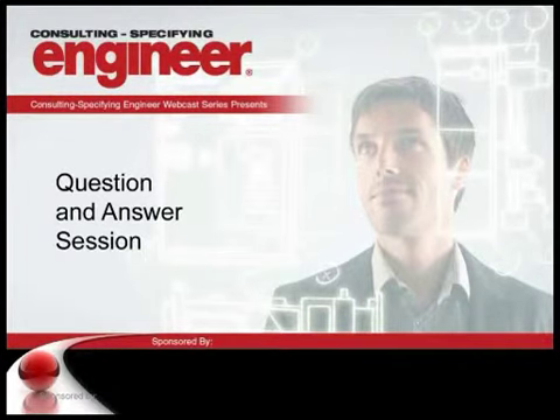Life safety is not limited, with the exception of what you can put on it by the code. But if you're over 150 kVA, you have to have one for life safety, one for critical, and one for equipment at minimum. And bigger systems would have even more than that. Thanks. Okay. Thank you, Jim.